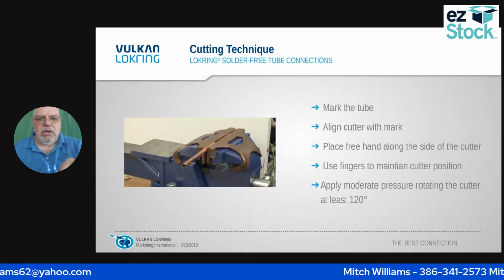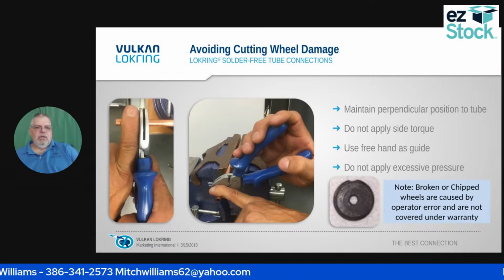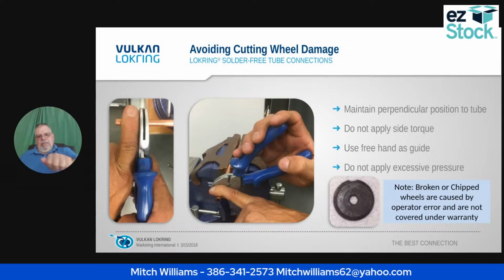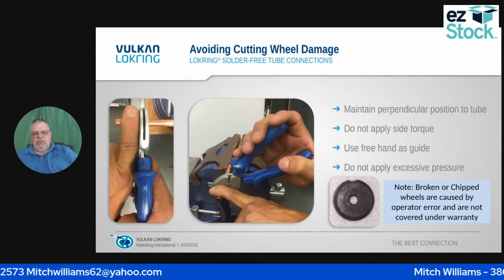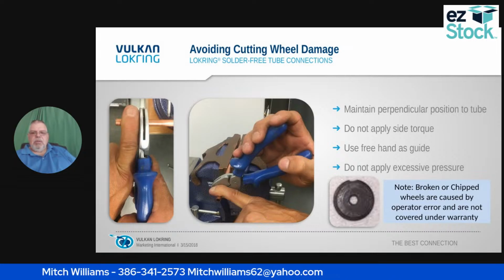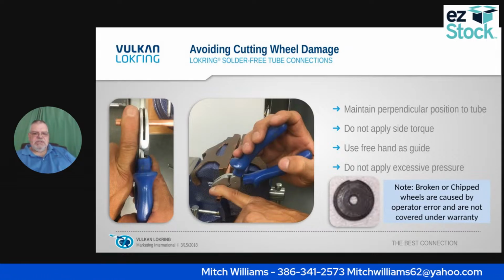That's why you keep one hand on it, so that you don't let the tubing cutter move. If you look right here, they're using one finger. Okay, I'm a 3-finger guy. I grab 3 fingers on it, and I make sure that my thumb is pressed right up against the unit itself, wherever I'm cutting. So I maintain the perpendicular position to the tube. Do not apply side torque. That's where it walks. Use the free hand as a guide, and don't apply excessive pressure.